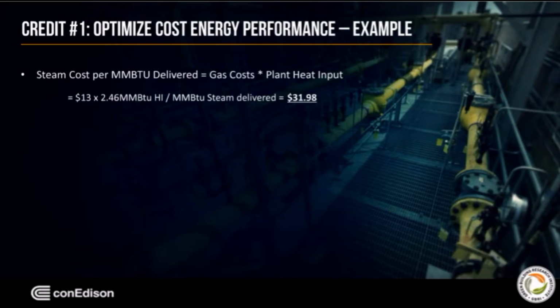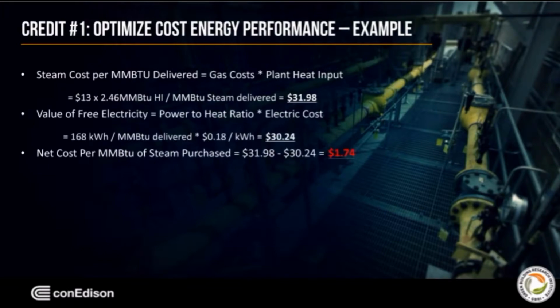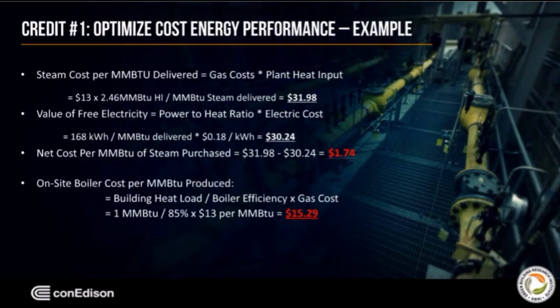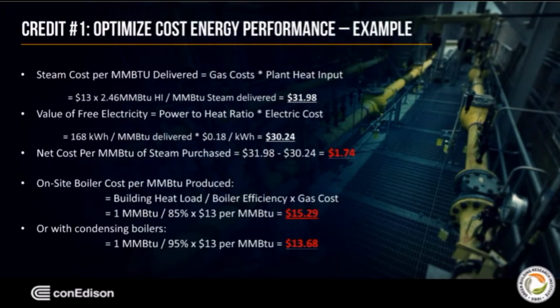The steam cost for 1 million BTU delivered equals the gas cost multiplied by the plant heat input, which is $13 times 2.46 million BTUs divided by the 1 million BTU delivered, which equals $31.98. The value of the simultaneously produced electricity equals the power-to-heat ratio multiplied by the electric cost, which is, as we learned, 168 kilowatt hours delivered by the 1 million BTU delivered times 18 cents, which equals $30.24. Now, the net cost per million BTU of steam purchased equals the $31.98 minus the $30.24, which amounts to $1.74.